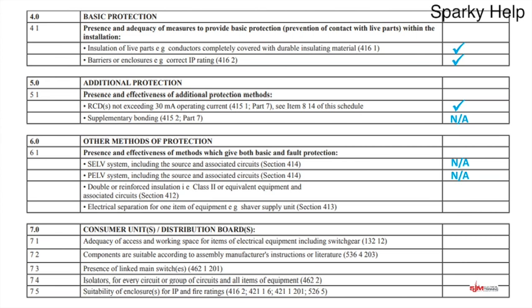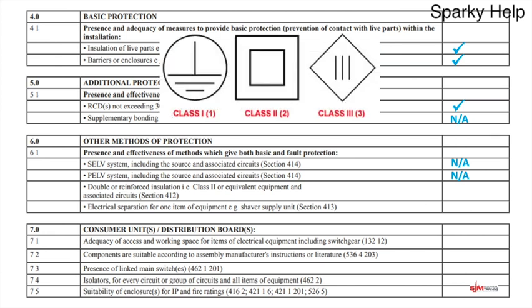Next, we've got double or reinforced insulation, class 2 or equivalent equipment and associated circuits. So this is the middle symbol. So class 1 equipment would have the earth symbol on, because class 1 equipment has to be earthed. Class 2 tends to not be earthed. Class 3 is going extra low voltage and doesn't have an earth on the output anyway. But we're looking at the middle one. So if you've got equipment that has got the square within a square as equipment, you'll be putting a tick in.